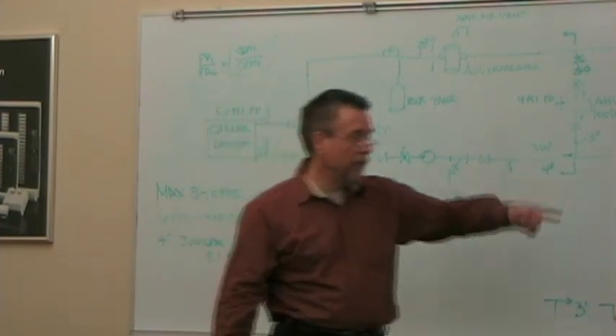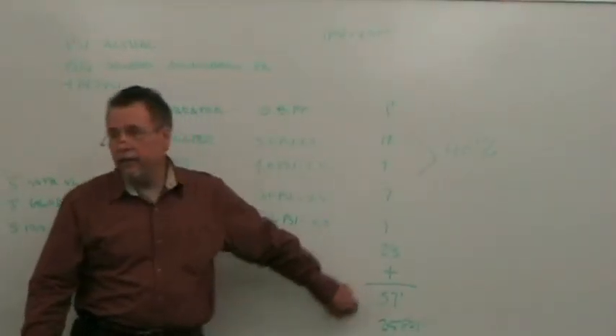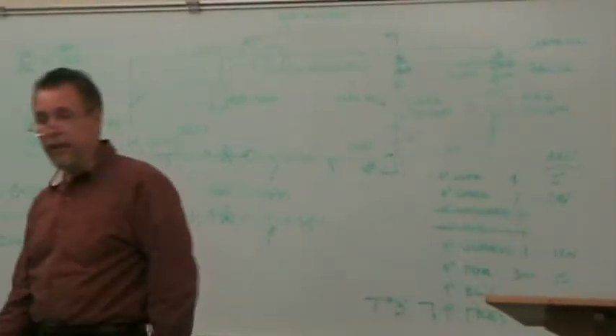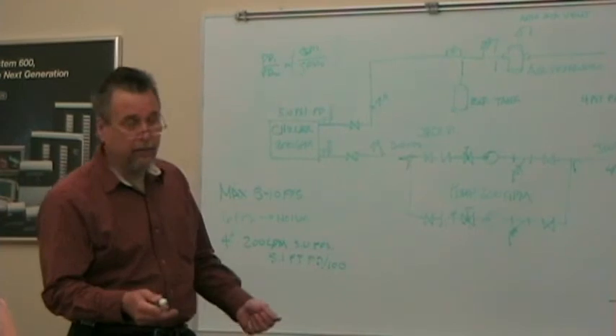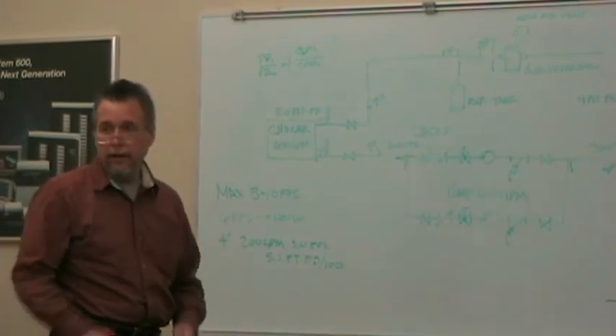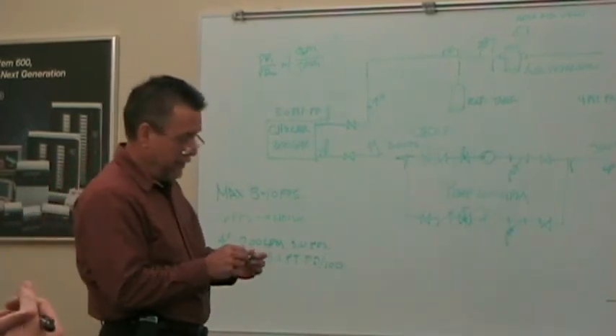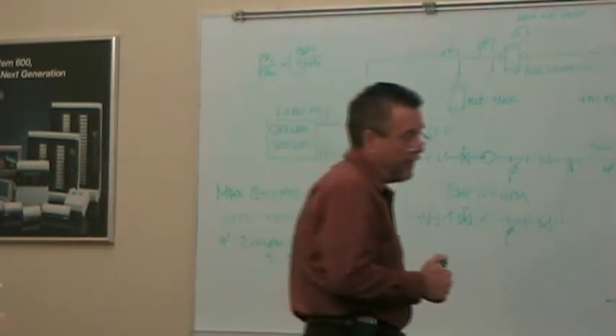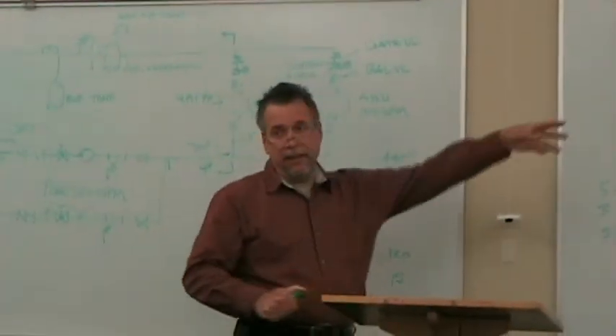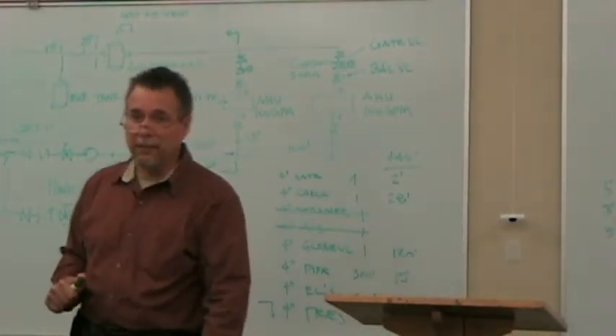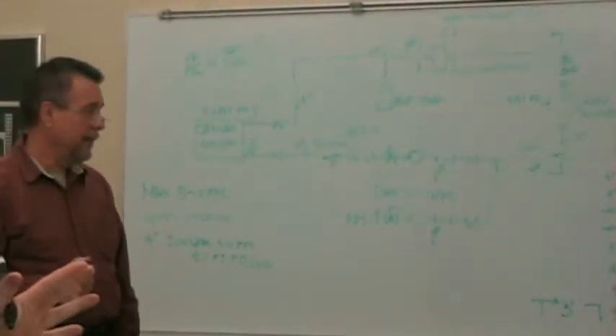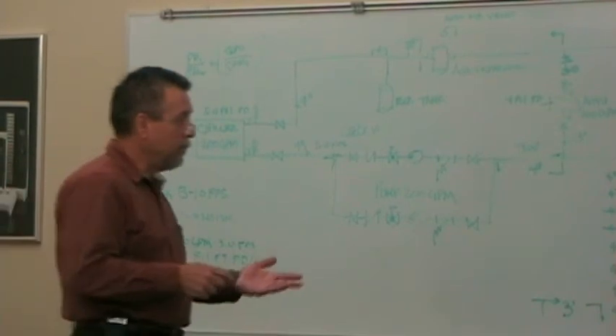What I would do now as a designer is put a safety factor on that. If I don't have a good set of drawings, the safety factor's higher. If I've got a good set of drawings, the safety factor's lower. And like I said the other day, there are some people that take things out to 2 or 3 digits past the decimal. That's kind of ridiculous. But so now I got a pump.